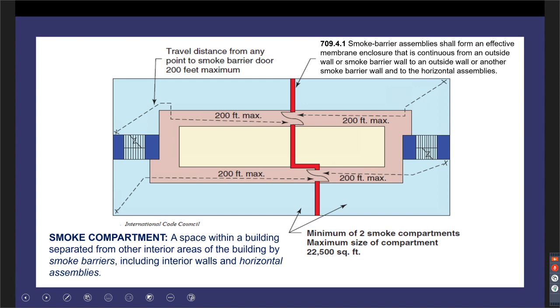So smoke barriers, from 709.4.1: a smoke barrier assembly shall form an effective membrane enclosure that's continuous from an outside wall or smoke barrier wall to an outside wall or another smoke barrier wall and to the horizontal assemblies.